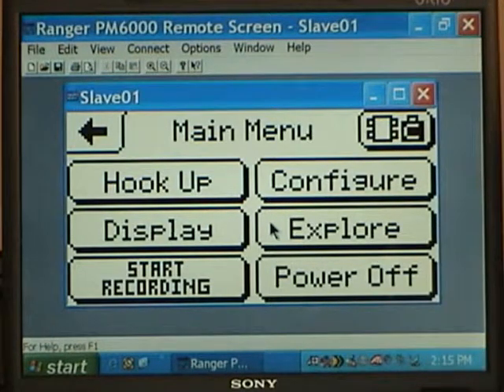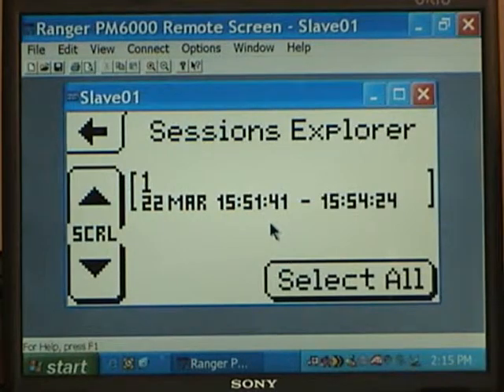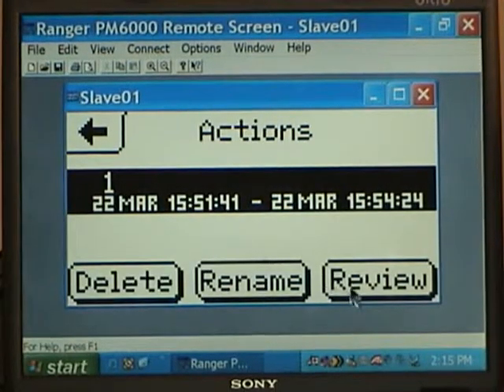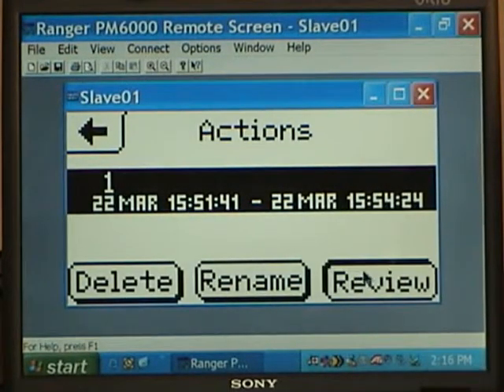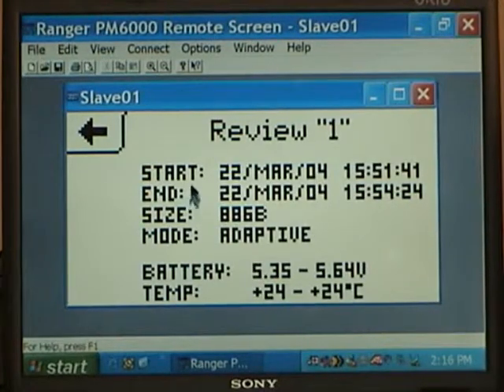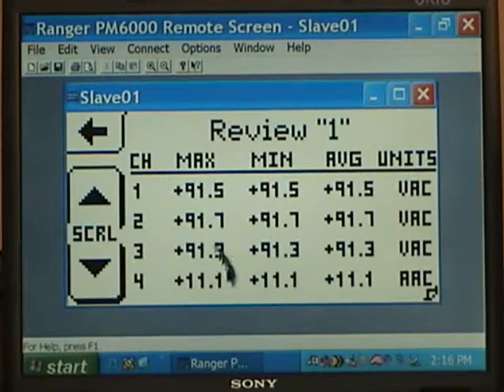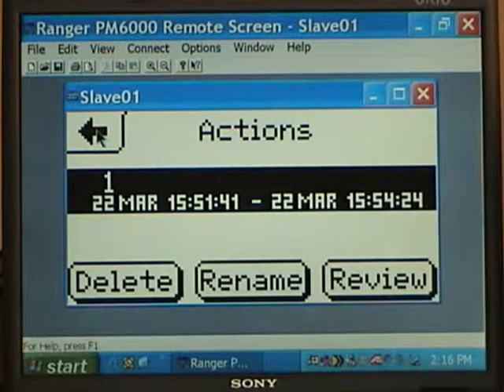In the Explore area here, you can look at old recordings that might have been made. There is one recording in here. If you were to click on it, you can review it by clicking on the review button here. It tells you when you started and stopped the recording, what recording mode you were in, the battery condition, and the temperature that this unit was subjected to. And we also record the maximum, the minimum, and the average of each of the recording channels. And you're allowed to see that immediately before you even download data.